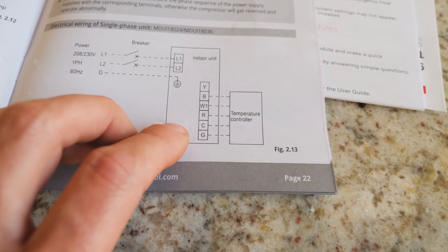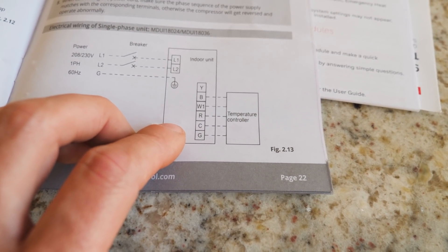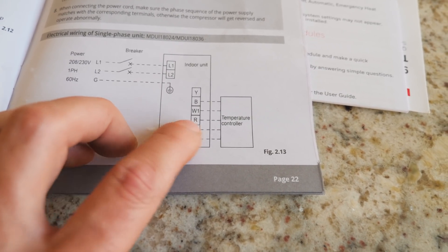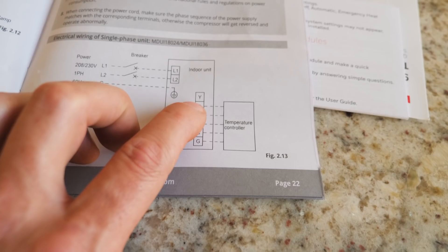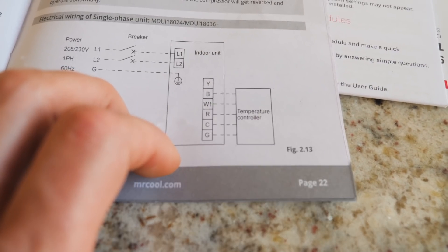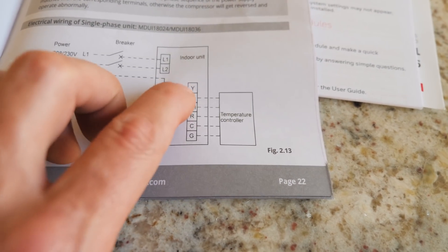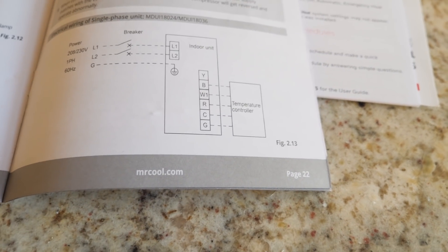But when you go to hook up the thermostat, this is the thermostat to the air handler, says hook up all these wires but there's no wire for the yellow for the compressor contactor. So I didn't plug it in and that's why my outside compressor wouldn't kick on. The air handler worked, the fan worked, everything else worked. So I went back, plugged in that wire and the compressor kicked on. The directions should be much clearer than that. Make sure you plug in your yellow wire.